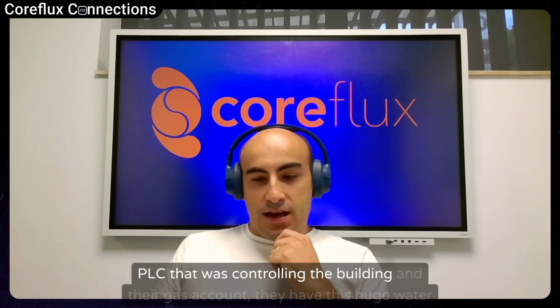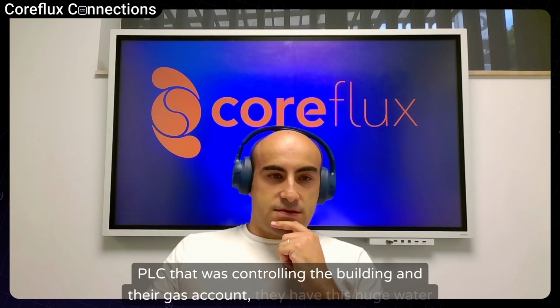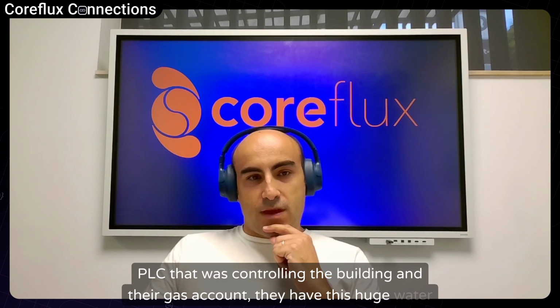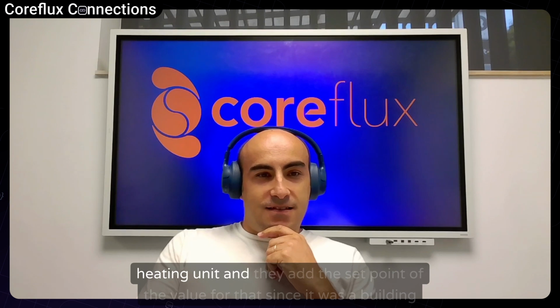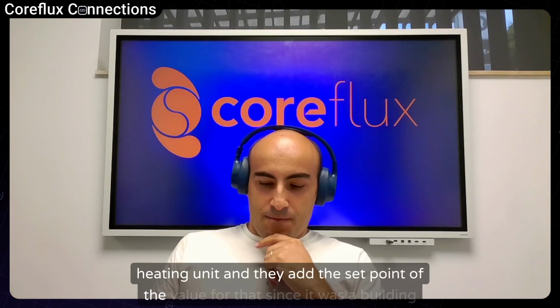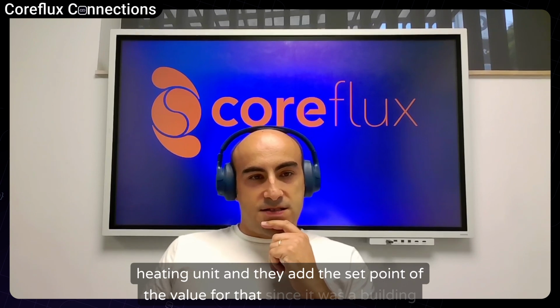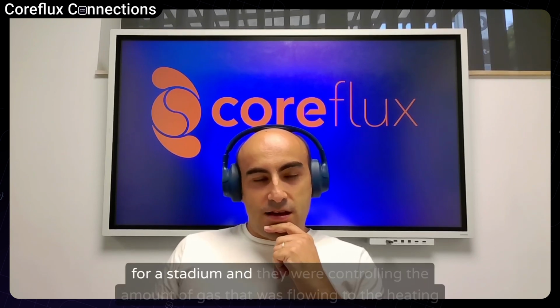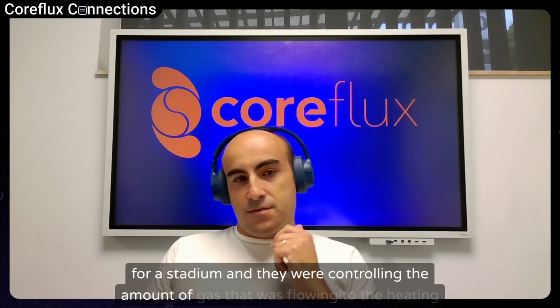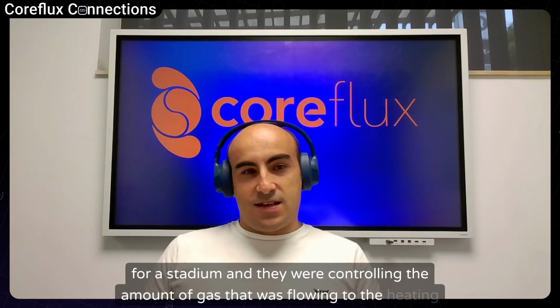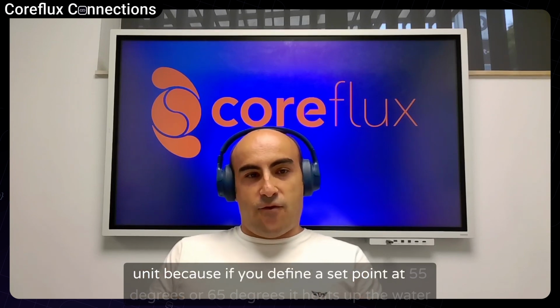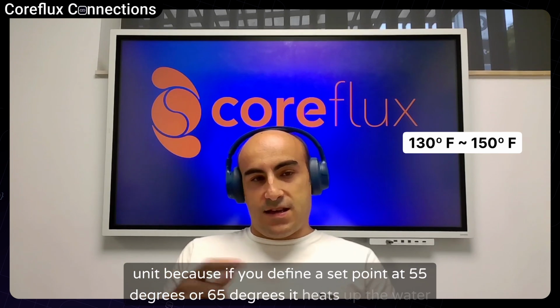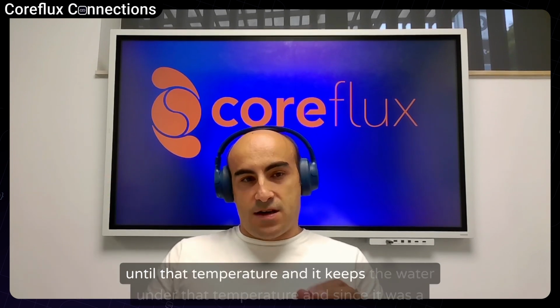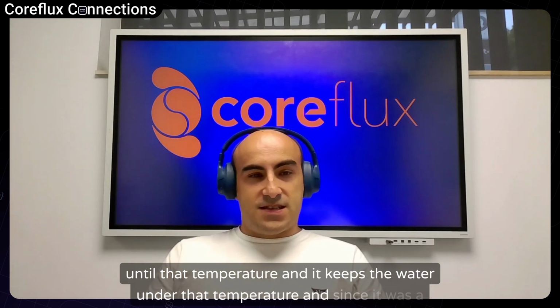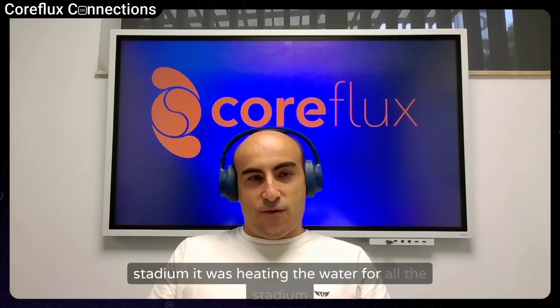So they had this PLC that was controlling the building, and their gas account, they have this huge water heating unit, and they had the set point of the value for that, since it was a building for a stadium, and they were controlling the amount of gas that was flowing to the heating unit, because if you define a set point at 55 degrees or 65 degrees, it heats up the water until that temperature, and it keeps the water under that temperature.